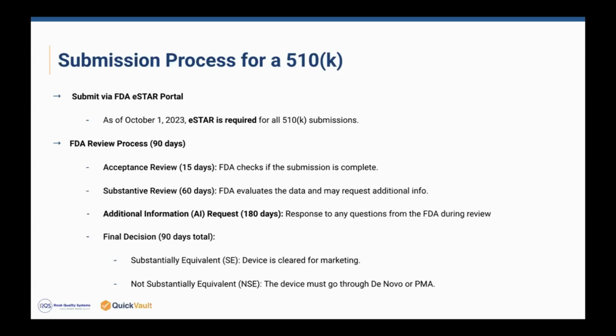So, the high-level FDA process: all the information you'll traditionally see online from the FDA and other resources says it's a 90-day timeline. We typically tell our clients it is 6 to 9 months. The reason for the difference really ties to this additional information. When you initially submit, there's no longer an RTA process; that was mostly eliminated with eSTAR. So there's an acceptance review just to check. The eSTAR really helps to weed out any of those issues, so it really streamlines that process. A majority of submissions are accepted in that first 15 days. Then it moves to the 60-day substantive review process.